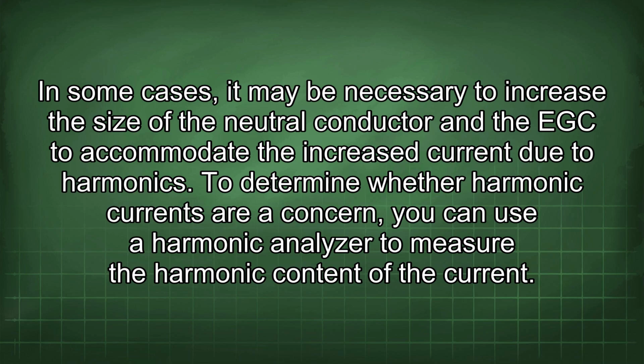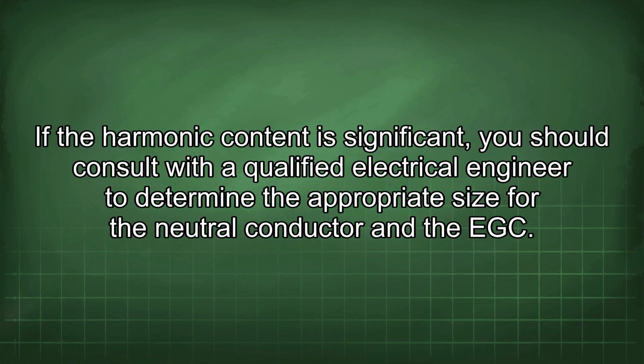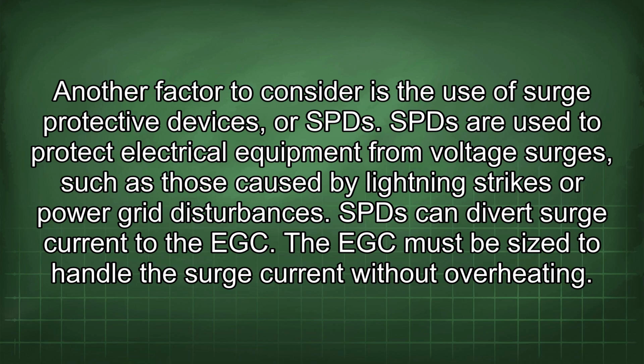To determine whether harmonic currents are a concern, you can use a harmonic analyzer to measure the harmonic content of the current. If the harmonic content is significant, you should consult with a qualified electrical engineer to determine the appropriate size for the neutral conductor and the EGC. Another factor to consider is the use of surge protective devices, or SPDs. SPDs are used to protect electrical equipment from voltage surges, such as those caused by lightning strikes or power grid disturbances. SPDs can divert surge current to the EGC. The EGC must be sized to handle the surge current without overheating.